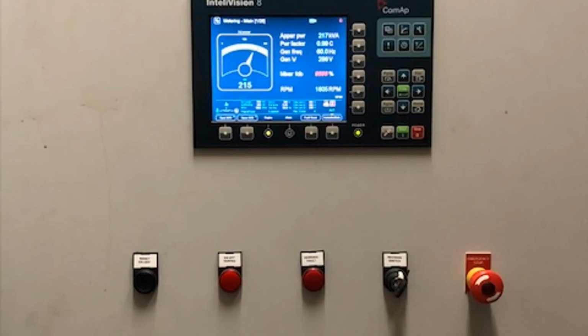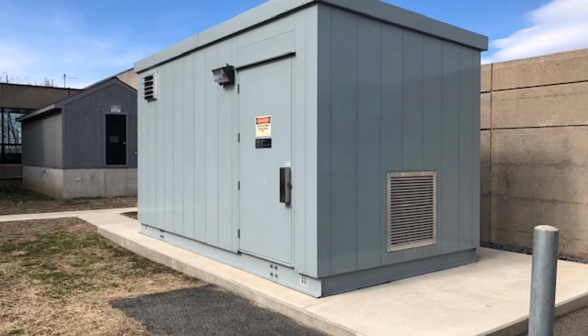The controls for our cogen units are somewhat sophisticated in that we are trying to produce power that is clean and can sync with utility. So before an engine can ever start producing power back to the facility, it needs to make sure it's within acceptable limits. And there are engine controls as well as electrical controls, lots of sensors and safety devices built into these systems. Once we're producing power off the engines, the power is sent over to a switchgear unit, which is ensuring that the quality is good enough to sync with utility, as well as controlling where that power is distributed within the facility.